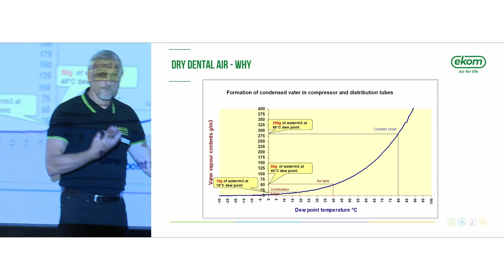But from the physics, at each cooling point, when we cool down the air, its capability to hold, to retain water vapor goes dramatically down. So when we cool down the air in the tank, we get 40 degrees Celsius because the tank acts as a cooler. Look at this - the air can keep only 50 grams. So the difference, 290 minus 50, 240 grams have to condense into water.